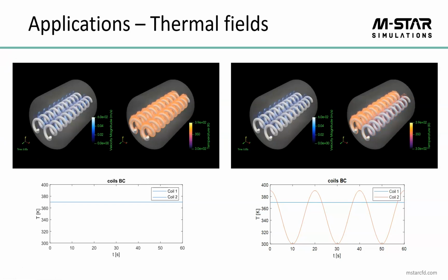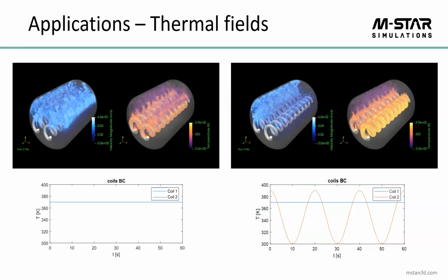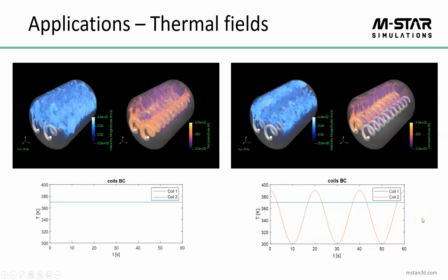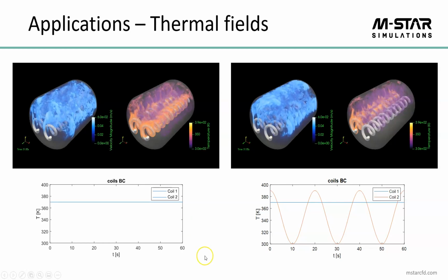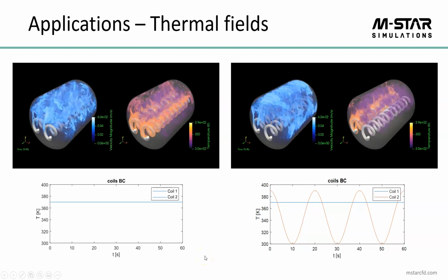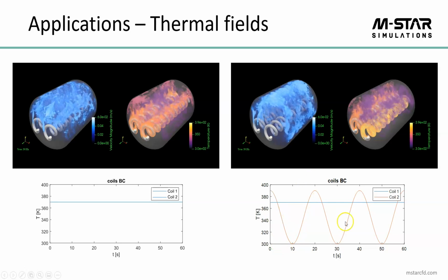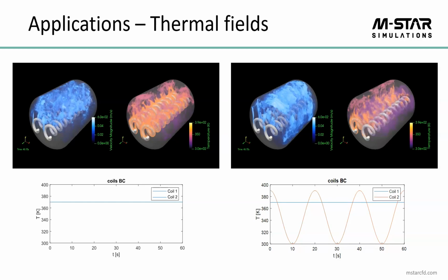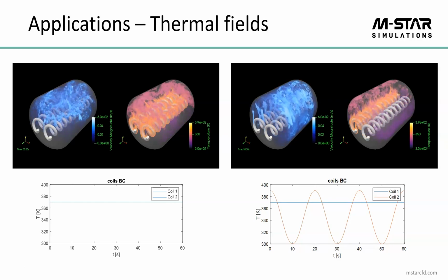Here are heating coils being turned on and off to characterize the net flow inside this oven as a function of the applied voltage. There's a lot we can get out of this in terms of the transient physics. And the one on the right here is a broken element, where the temperature is changing as a function of time. The one on the left is working properly, and being able to see these time-evolving physics and model them as they would occur in the plant, that's compelling. Again, the more closely we represent what's going on inside the plant, the more useful these predictions become, and that's what we can do across 3D space and time.